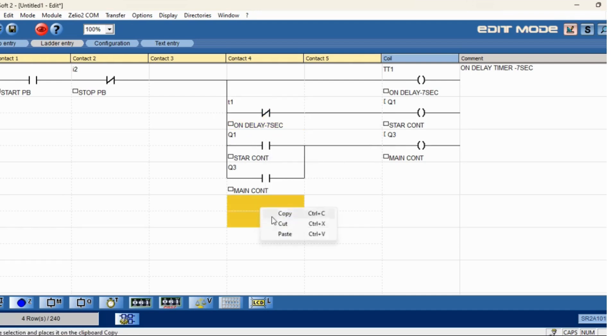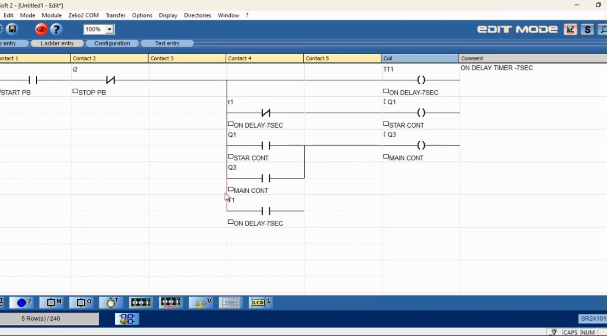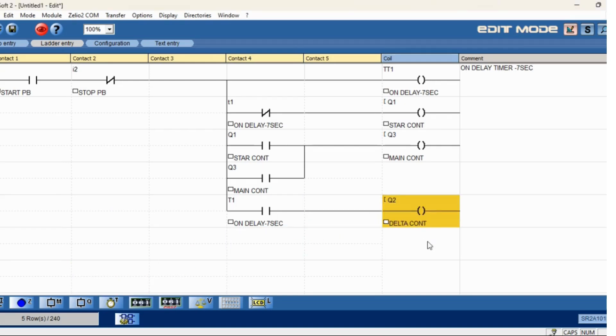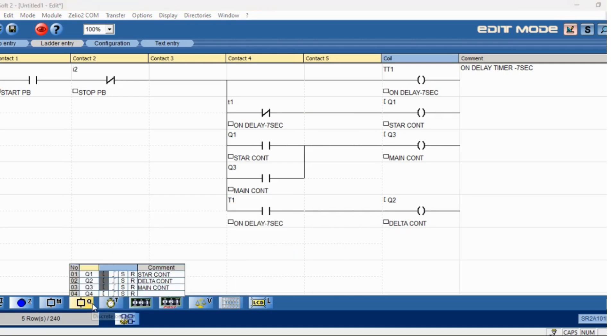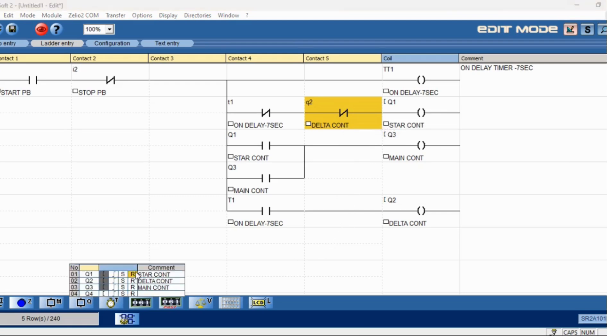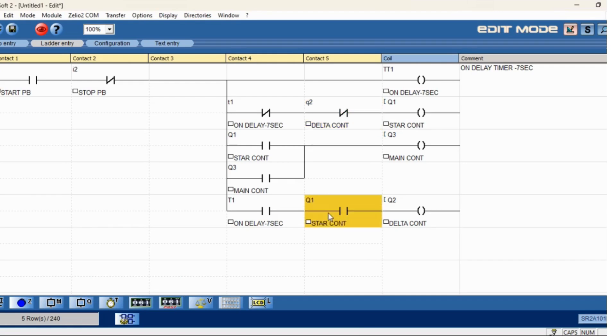Next will be the delta circuit. Delta is parallel. For star the timer is NC, so here NO will come for delta. You can copy and paste and change to normally open. For the interlock: when star is enabled, delta should not be activated; when delta is activated, star should not be enabled. We will use reset delta and star contacts as normally closed for the interlock.